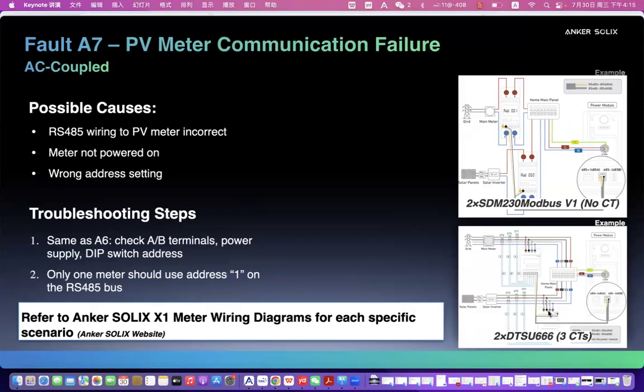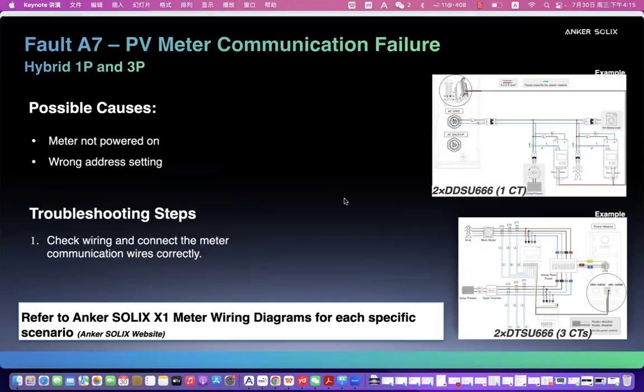If you connect the well-known three-phase meter, it should connect to 3 CTs. For the PV side, if these CTs are on the wrong phase or in the wrong direction, it will not show errors. You should turn off the solar inverter to judge and make sure it is correct, and see the application's energy power flow diagram. Otherwise it will seem all good. So installers need to check this point. It's similar to A7.